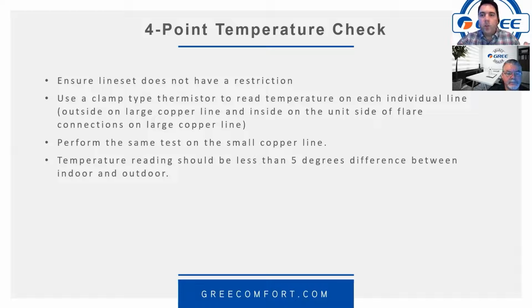Those two temperatures should be almost the same, within 3 to 5 degrees of each other, indoor and out. If that is true, then there's no restriction in between the indoor and out in that particular pipe. Very good. Very helpful tip.